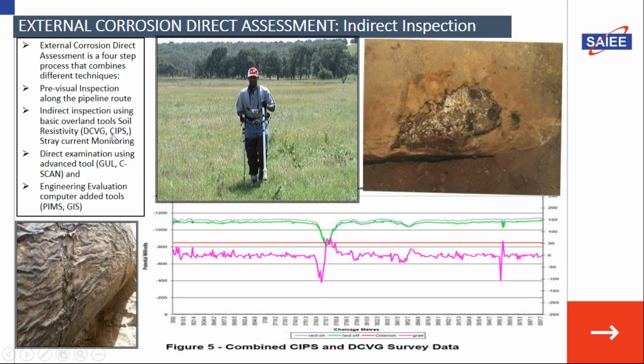You also do what we call a close interval potential survey. Because you've injected current into the pipeline, you're affecting its voltage, which is the potential of the pipeline. Under normal circumstances, a new pipeline's potential is minus 0.5 volts. Once you inject current, you increase that to a higher electronegative number.